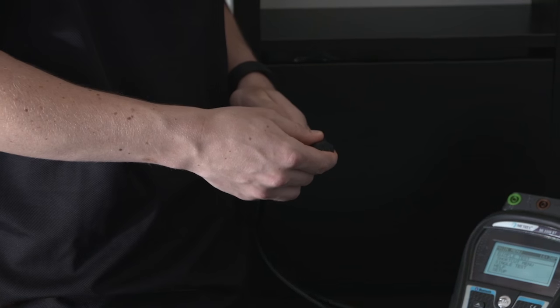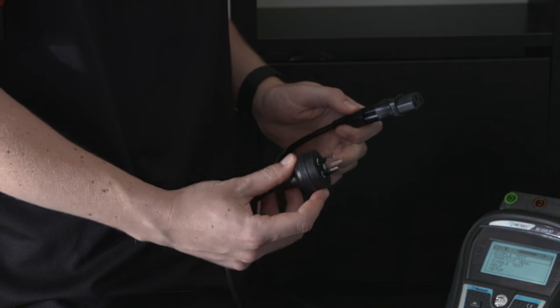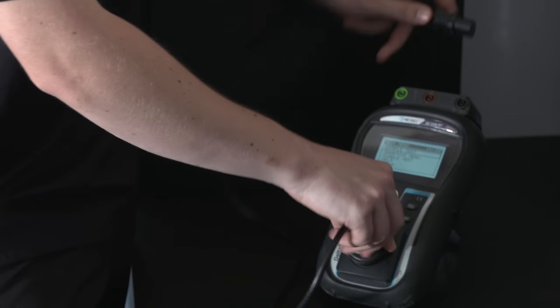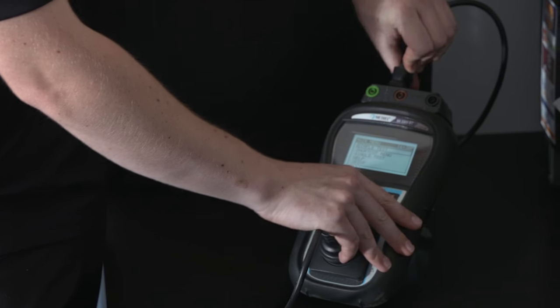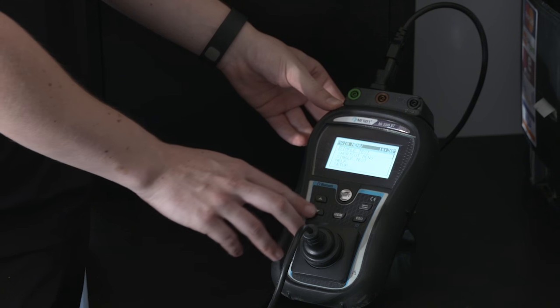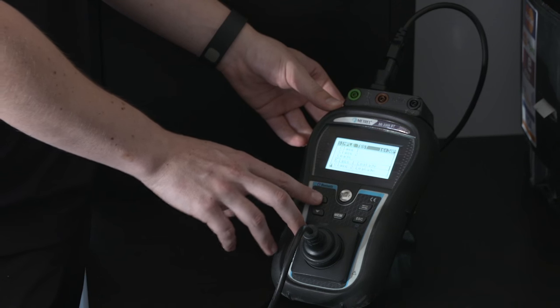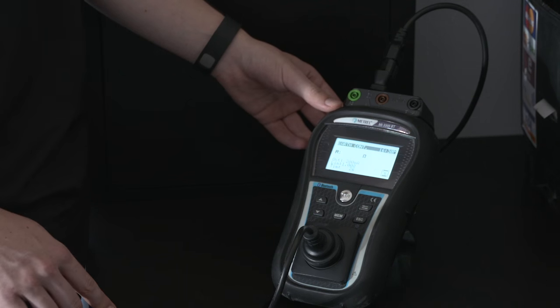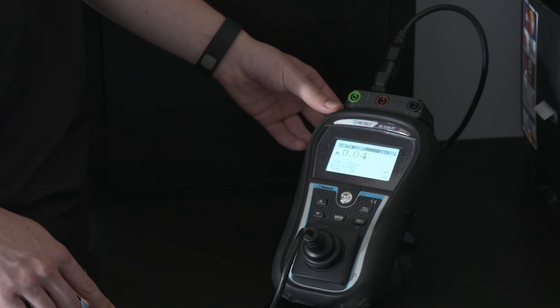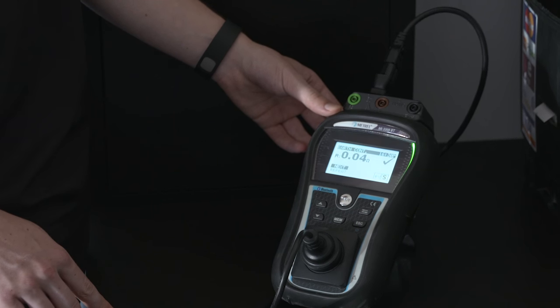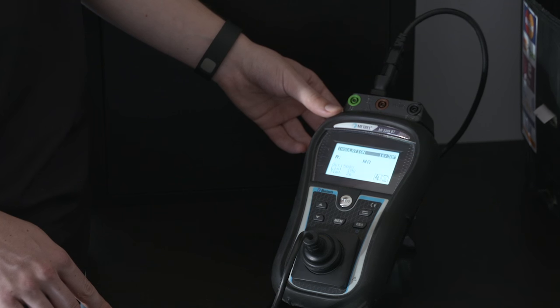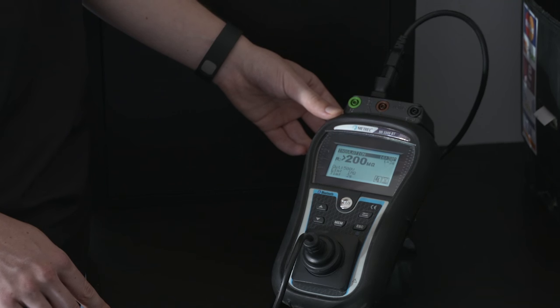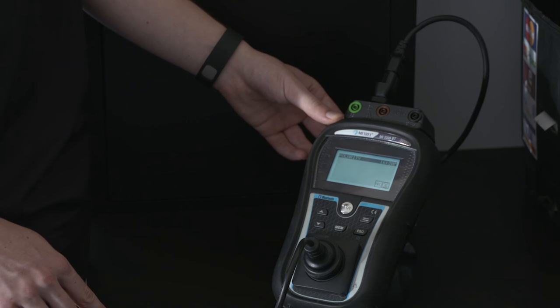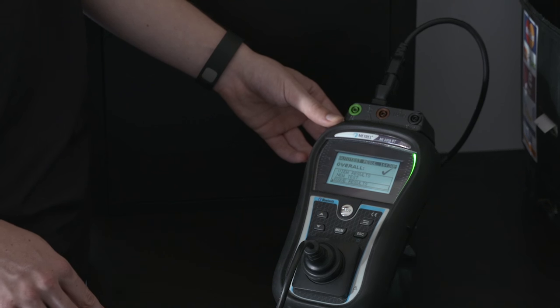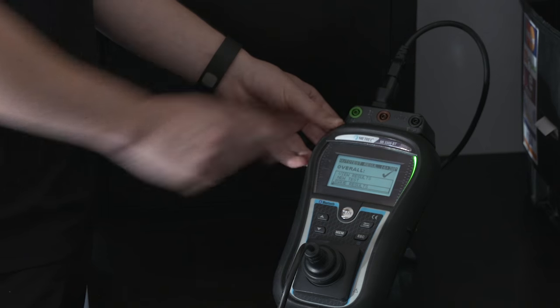You'll need an adapter. This adapter converts the clover leaf to a regular IEC. Plug both ends of the lead into your appliance tester, and through the menu, we'll select a lead test. The green light indicates a pass.